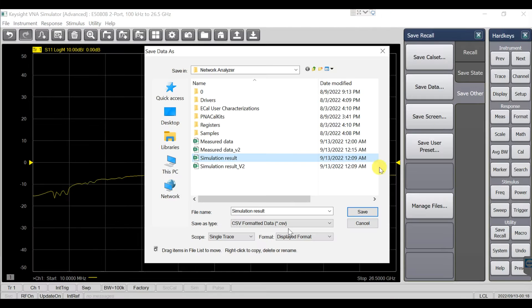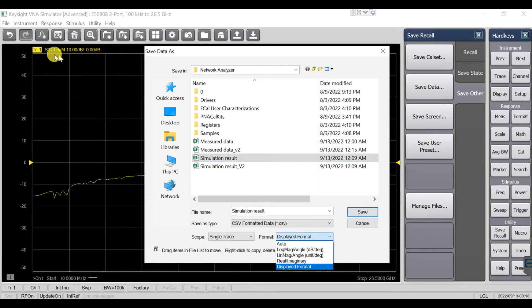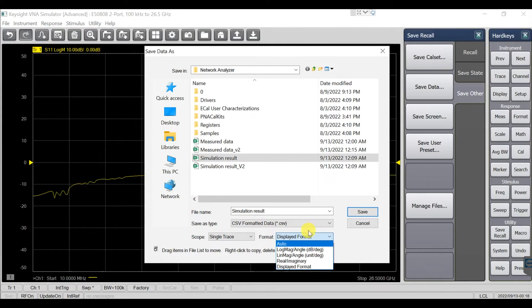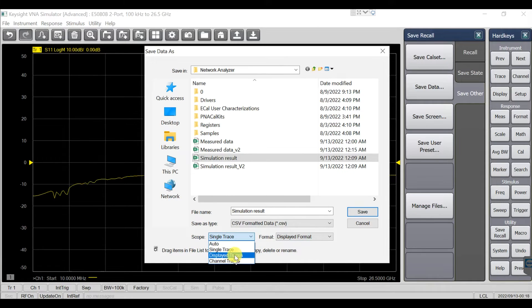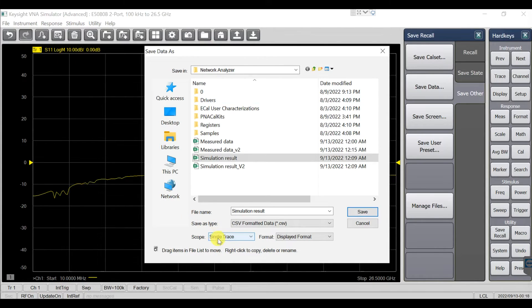When saving the result, be careful with your format. Usually we choose Display Format, which means the format currently displayed in the VNA — the data will be saved according to that format. You can also choose log magnitude/angle, linear magnitude/angle, or real and imaginary. If you choose Auto, it will automatically pick a format. It's better to choose Display Format. You can also select single trace or display trace.